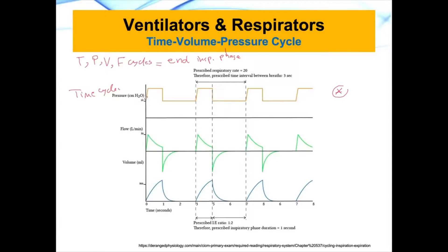Remember that this ventilator is actually time cycled — we are using pressure in it. It's called pressure controlled, but it's a time cycle ventilator. Pressure control means you are asking the ventilator to increase the pressure and hold it for a certain period of time, so you can control it with the pressure. And then after a certain period of time, you close the inhalation valve and open the exhalation valve for the patient to exhale. That is a time cycled pressure controlled ventilator.